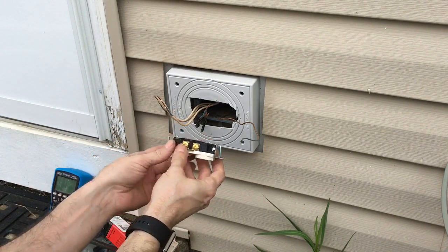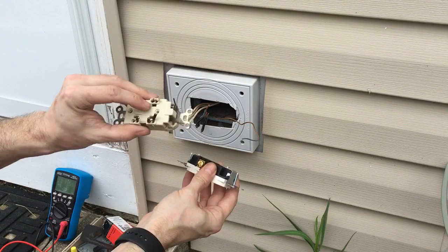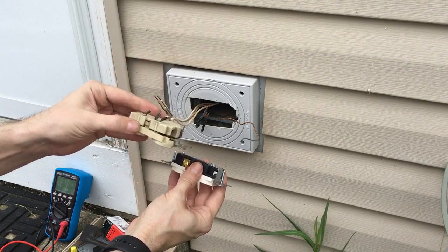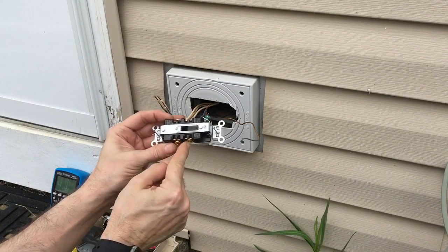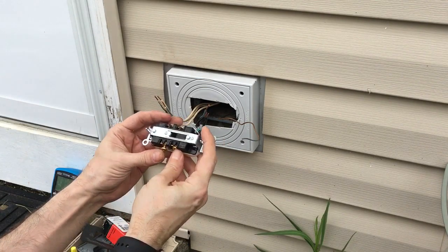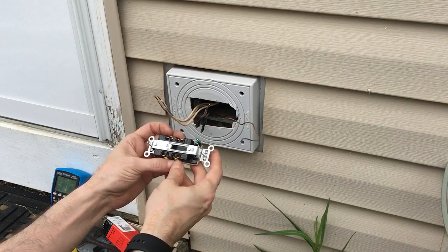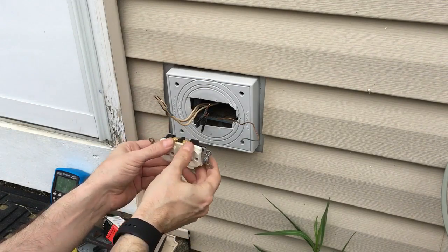Now you can either put the wire in, it snaps into place, and use a screwdriver to pop the wire out. This is actually illegal now. They don't have these. I actually prefer to usually wrap the wire around the actual screw terminal itself. But again, for me to daisy chain 2 other circuits off of the live here, I'm going to have to actually use the screw mount posting that they have here.